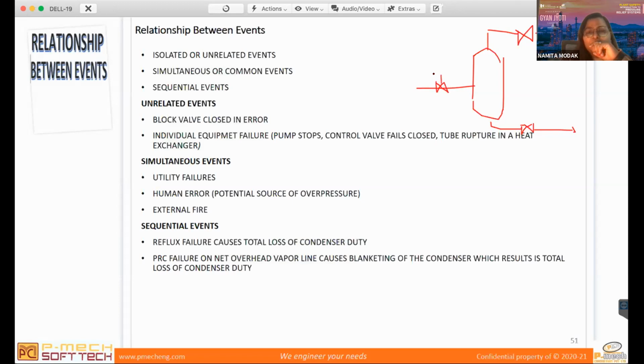Okay. So let's say my control valve fails. It's an individual scenario, right? Nothing else is affected because of this control valve failure. If my vapor is blocked in, it's only vapor blocked in, because my liquid is normally flowing out. But let's say my vapor is going to a compressor. Here, downstream of the vapor, I have given a compressor. Okay. Now imagine a scenario where you have a liquid blocked in. When your liquid is blocked in, I mean the flow is not passing through the liquid line.